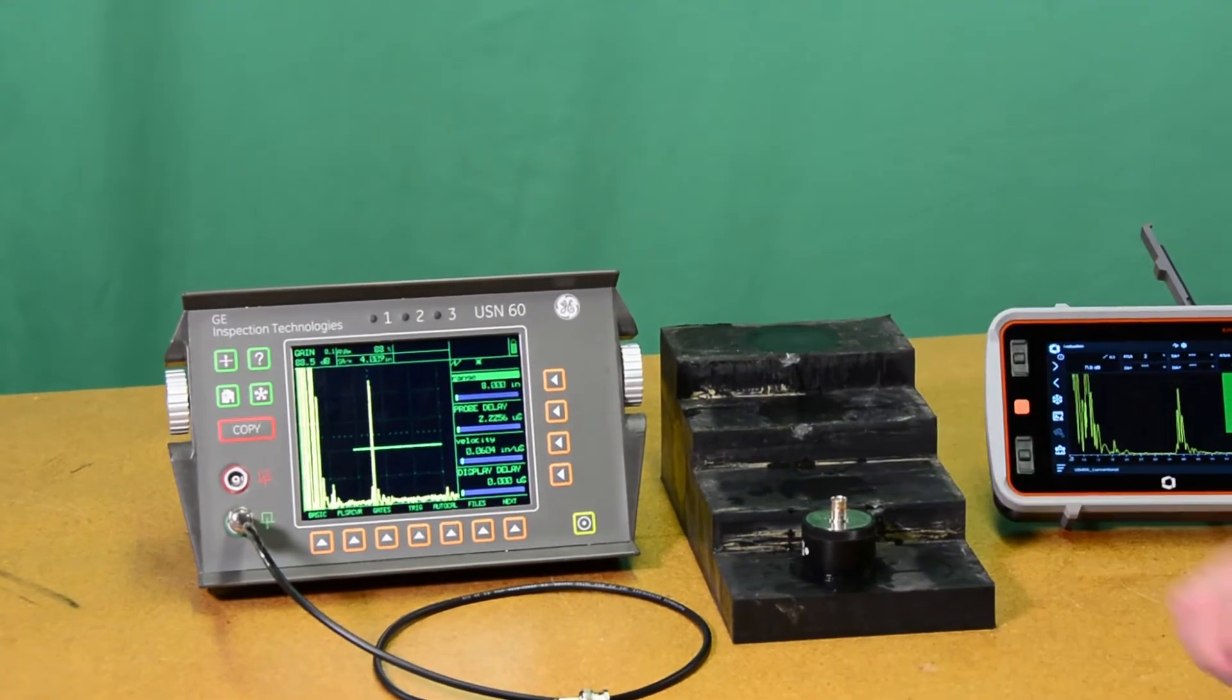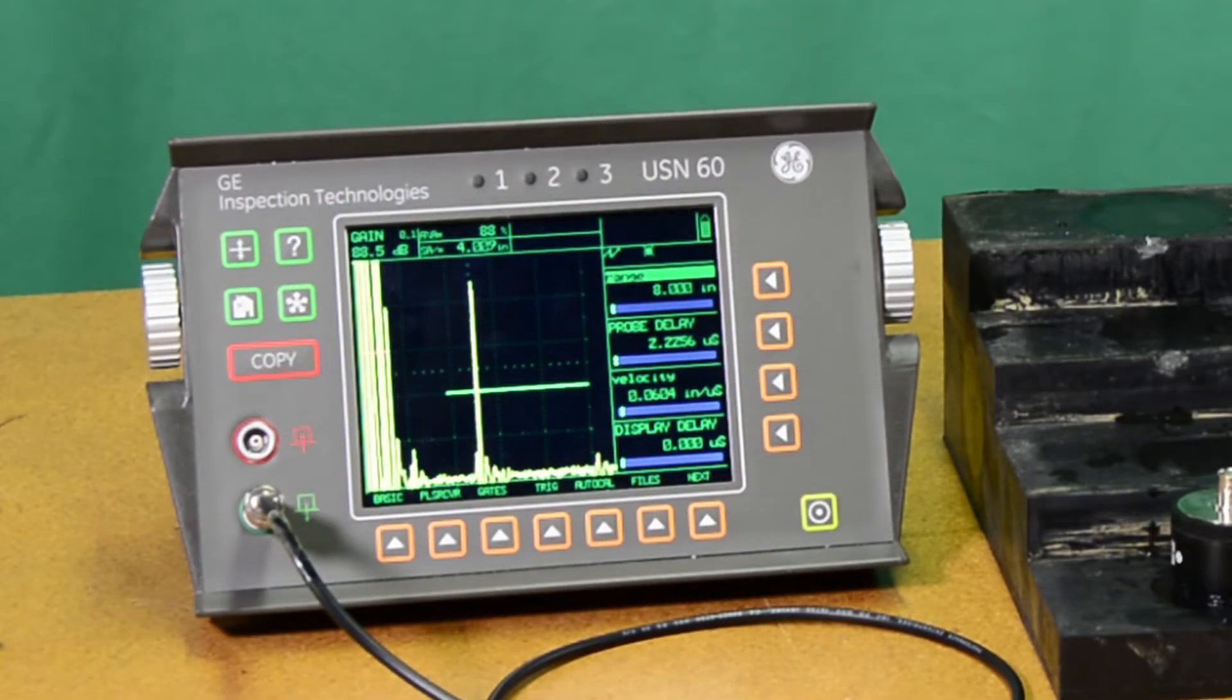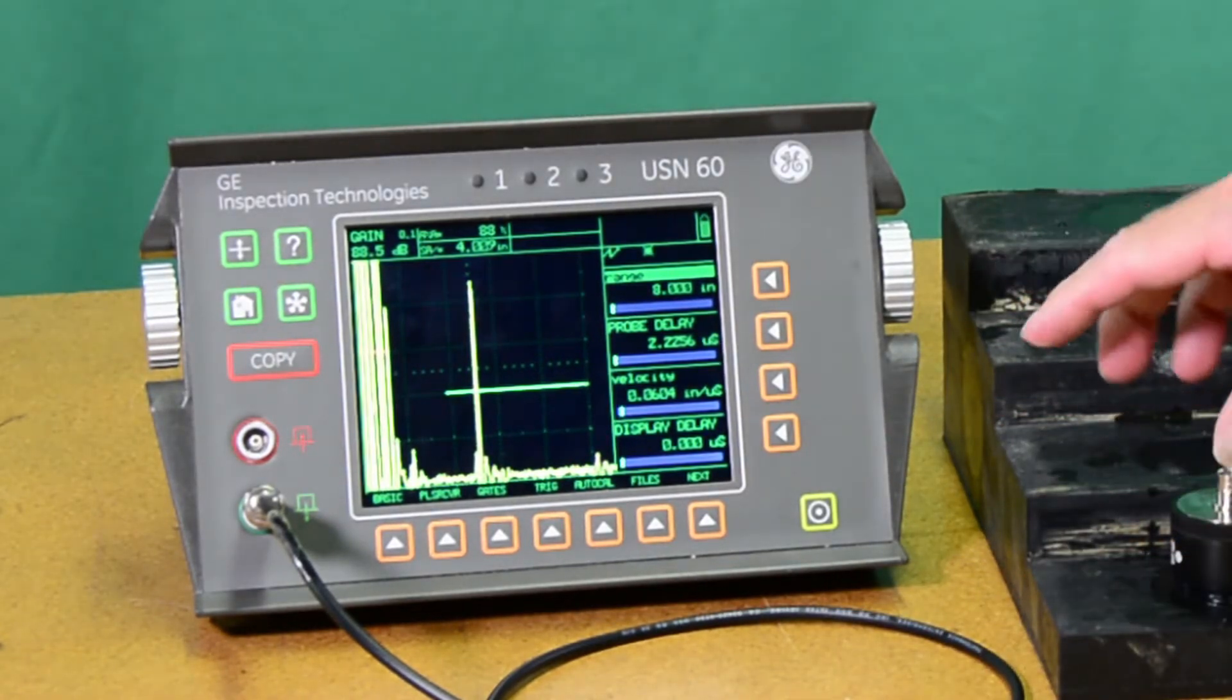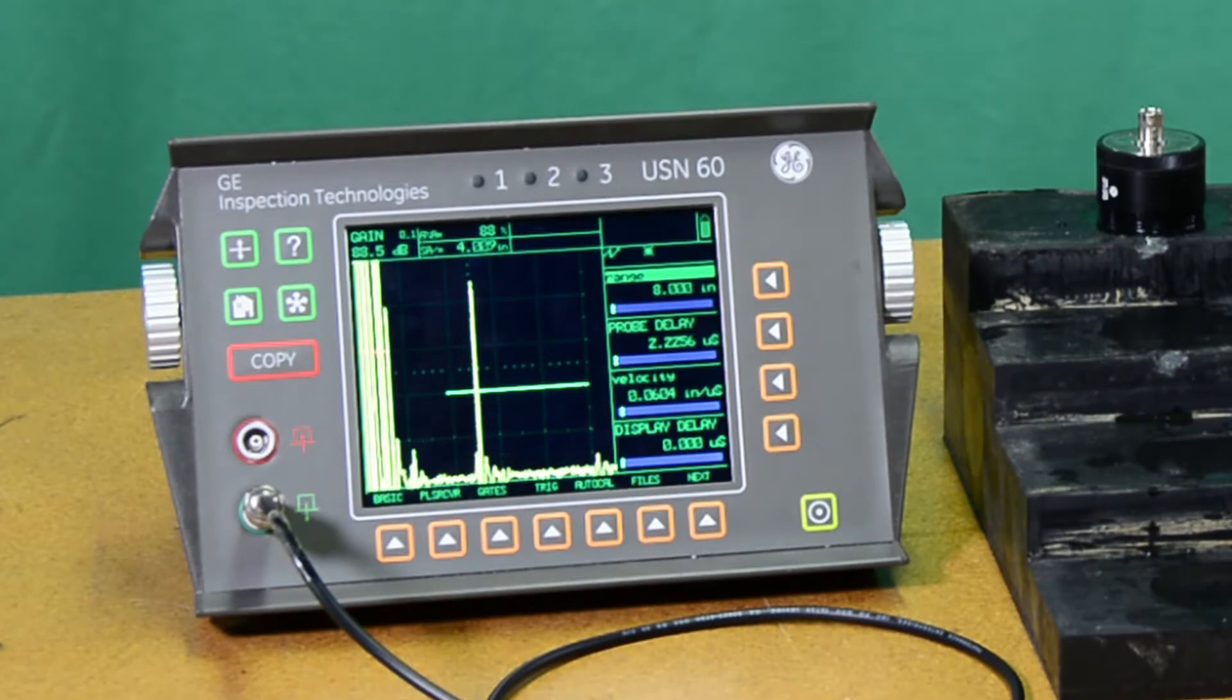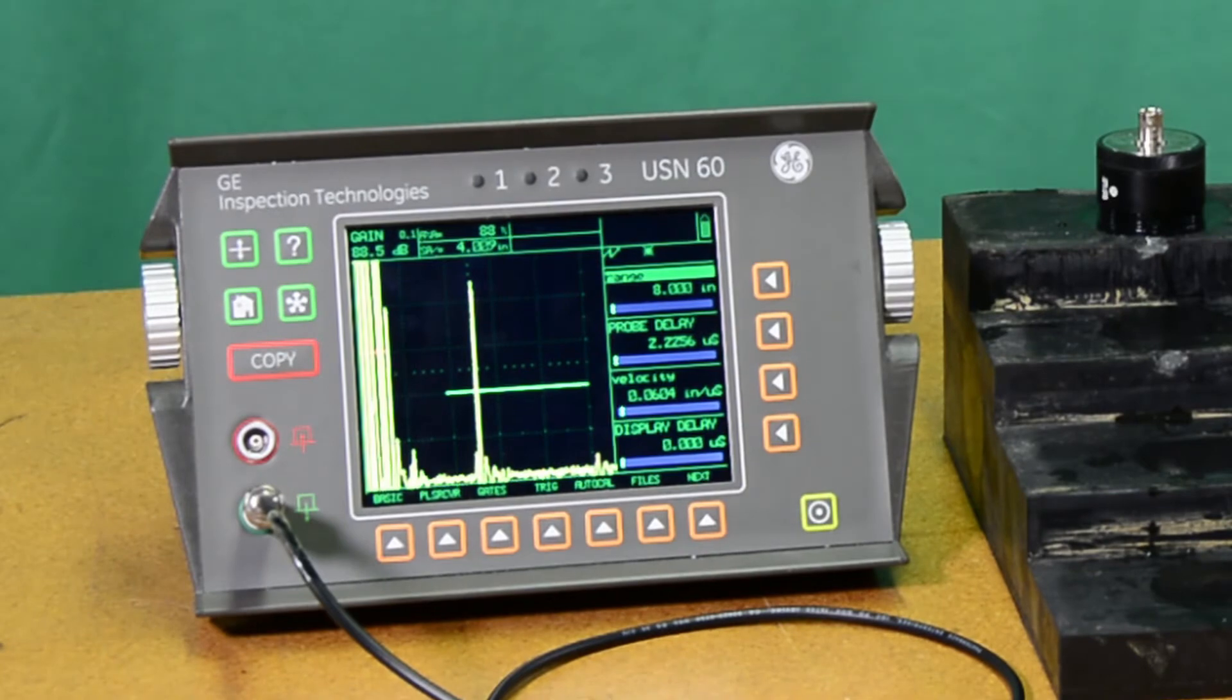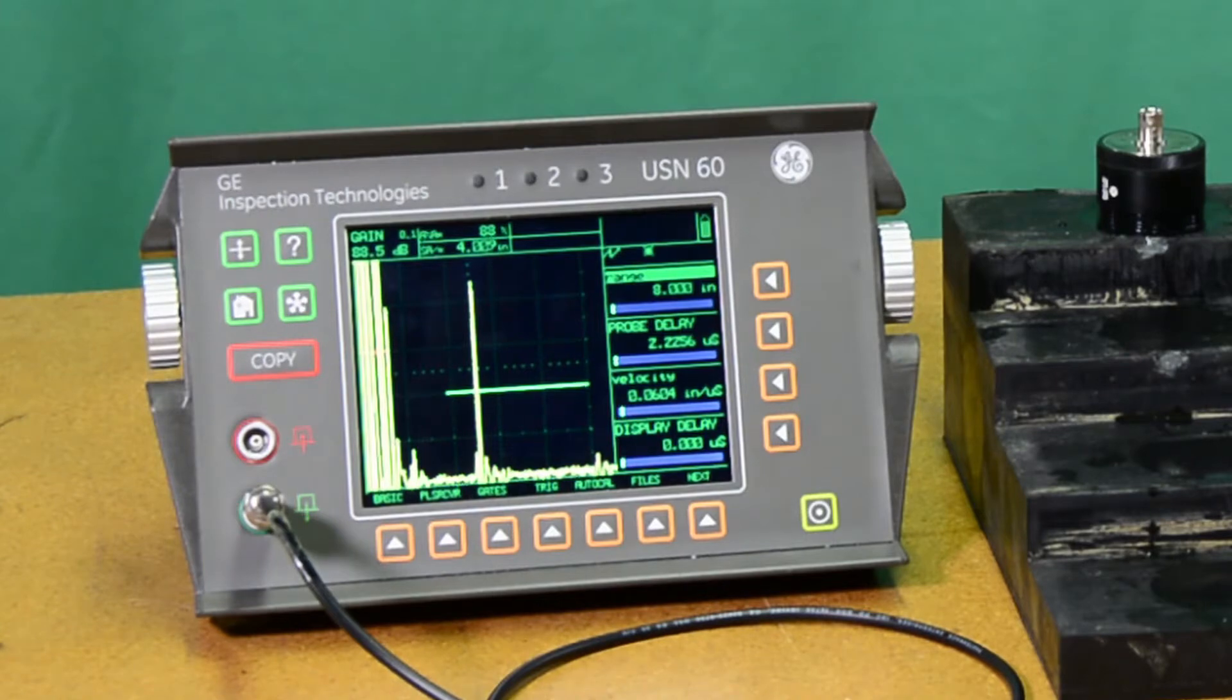One of our classic instruments, the USN 60 was our previous benchmark for this test. It had a 450 volt pulsar, square wave pulsar adjustable out to a thousand nanoseconds, one microsecond pulse width. On the screen I have frozen the signal optimized for setup with this probe looking at the 4 inch thickness of the rubber step block. You see the echo at 80% full screen height, actually a little over about 90% and gain set at 88 and a half dB to accomplish that.